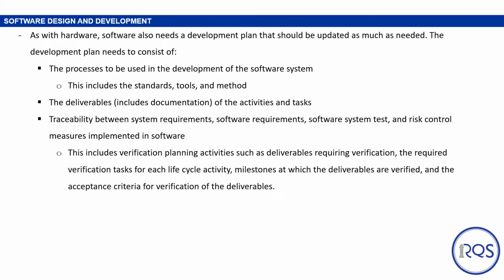The development plan should also consist of the deliverables, including the documentation of the activities and tasks performed. This is the same as hardware requirements. The development plan also needs traceability between system requirements, software system test, and risk control measures implemented in the software. This is also similar to hardware requirements.